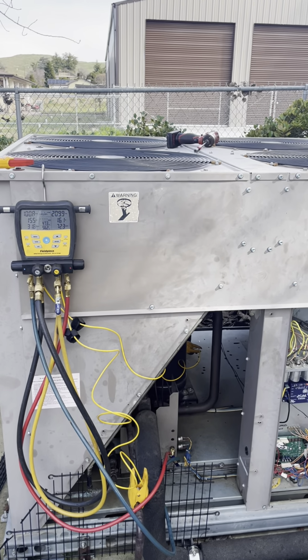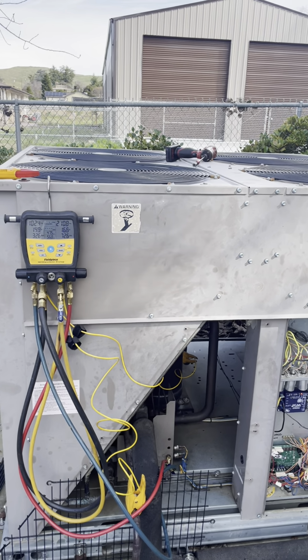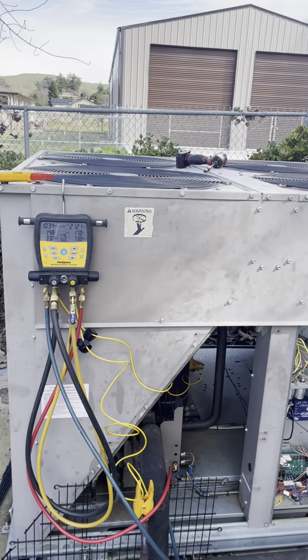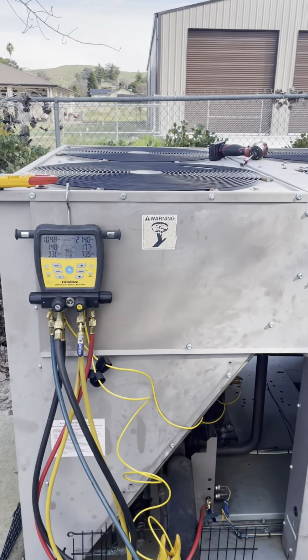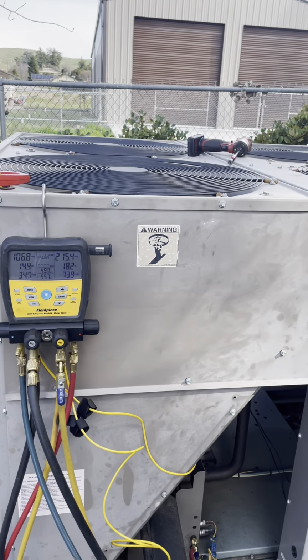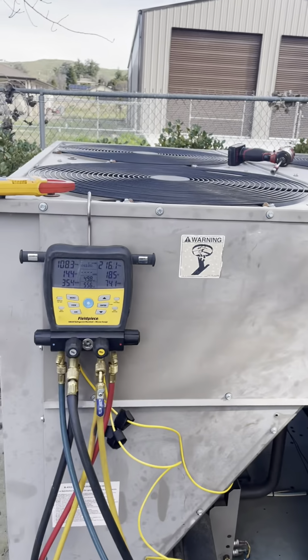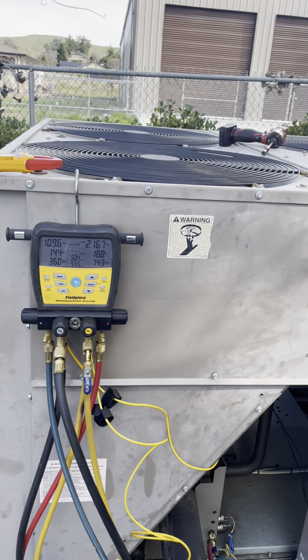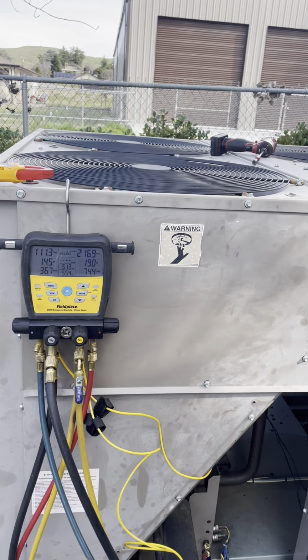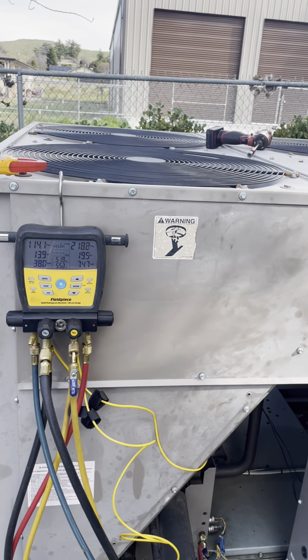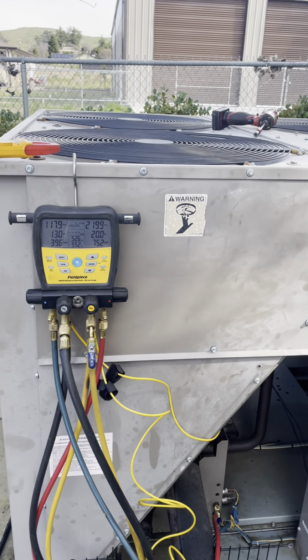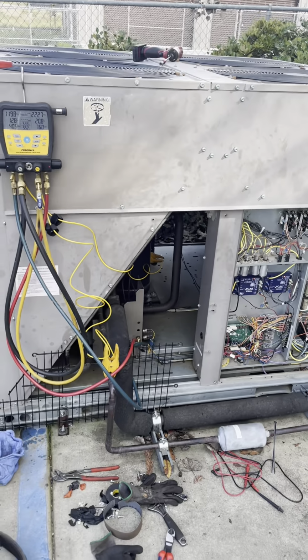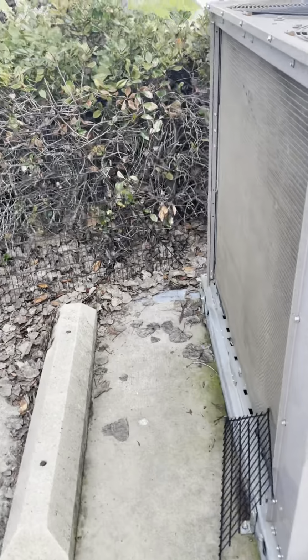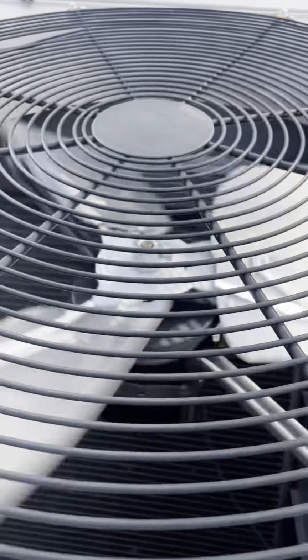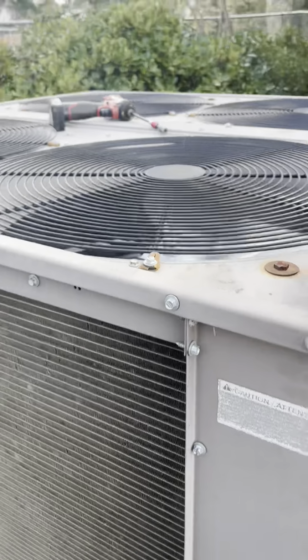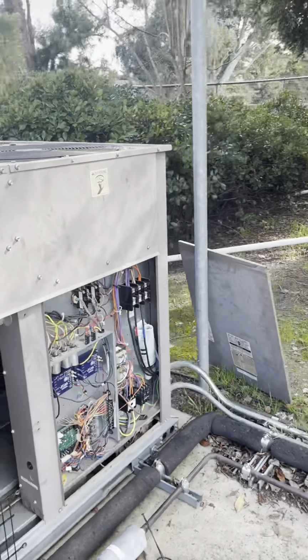So now that we have the thermistor strapped to the discharge line, we can actually monitor the temperature more accurately. For now, we have the modules adjusted through the app, and we're able to maintain somewhere around 80 degree liquid saturation. My supervisor was good with that, and I'm good with it too, because it's been running this whole time. So yeah, that was a pretty good one. Also, this fan right here sounds pretty crappy. So we went ahead and got approval to get a new replacement fan, so I'll be doing that now.